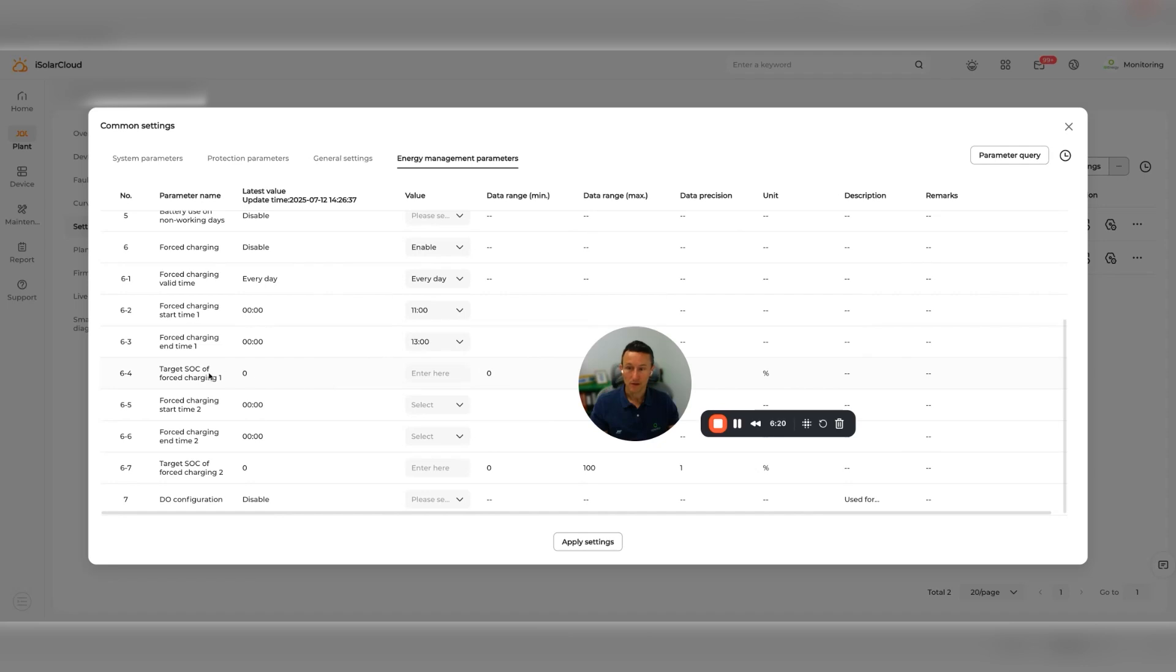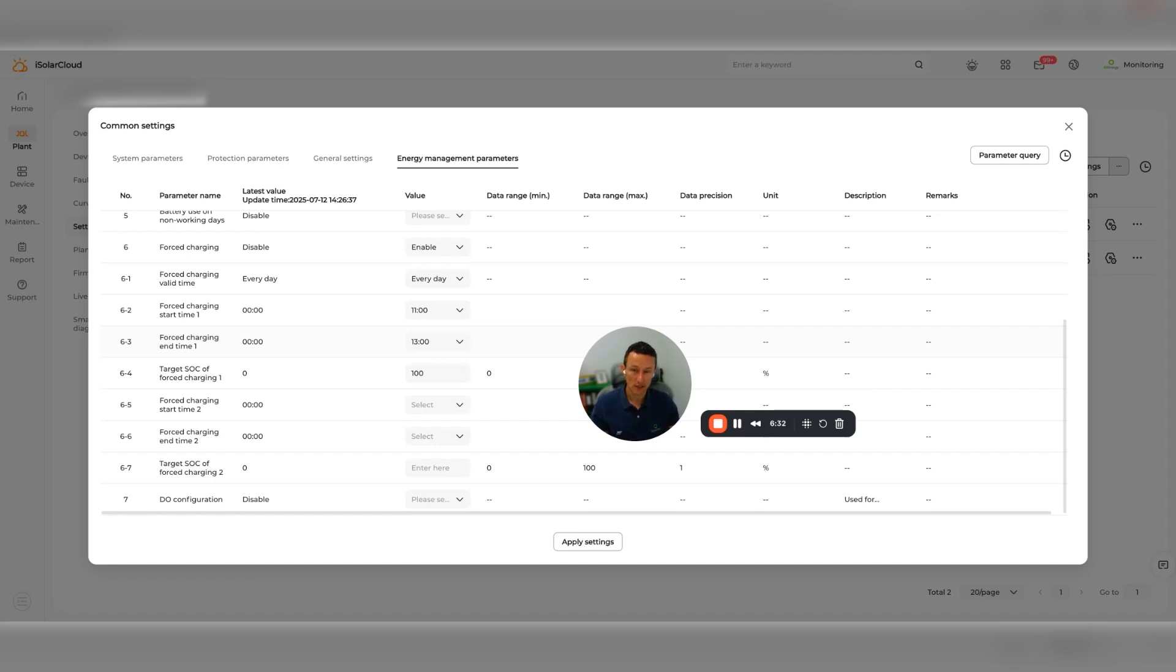And then this part here, you have to put your target in. The target state of charge for force charging - you want to put that at 100%. Whether or not it gets there is obviously dependent on how much time and inverter capacity you have. The other thing that is worth noting here is when you set this up.